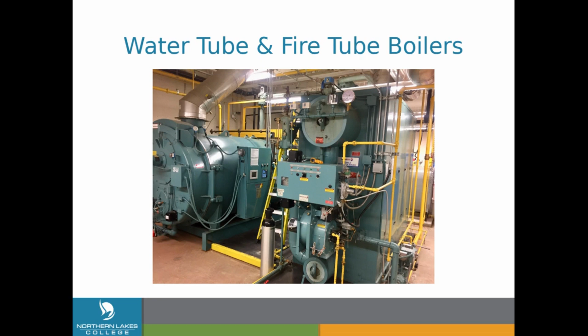The next few slides are pictures from our equipment on site at the Peace River Power Lab. Water tube and fire tube boilers. These are both Cleaver Brooks package boilers. They are high pressure boilers running at 125 psi. The boiler on the left is a fire tube boiler and the one on the right is a water tube or a flex tube boiler. In the fire tube, the fire is in the pipes and the water is on the outside, whereas in the water tube, the water is in the tubes and the fire is on the outside.